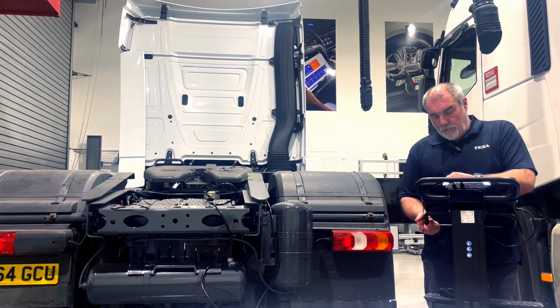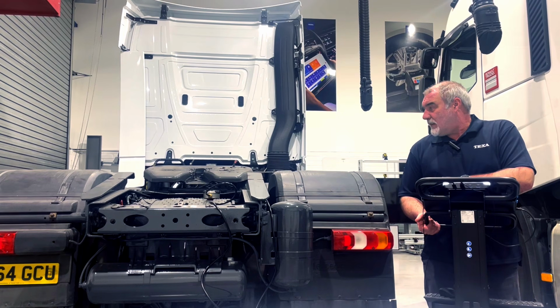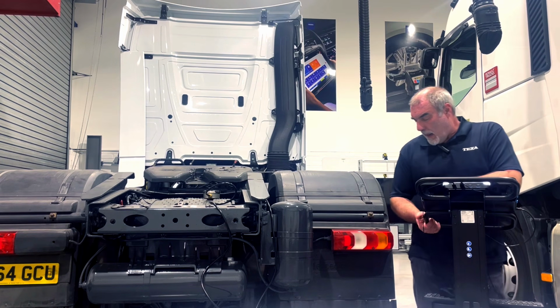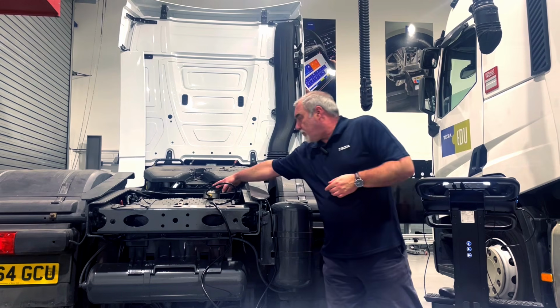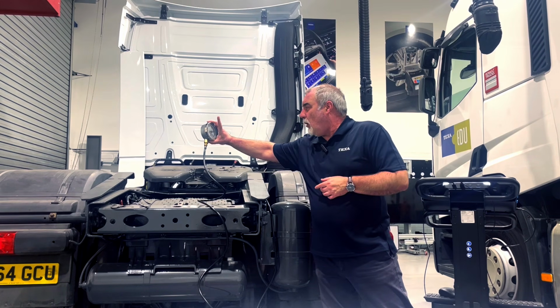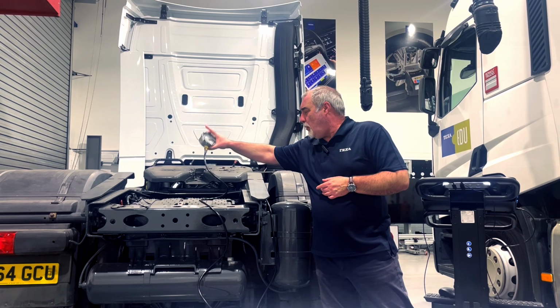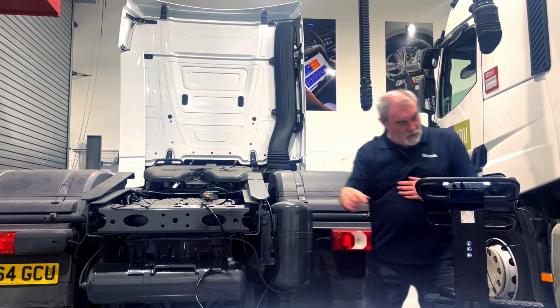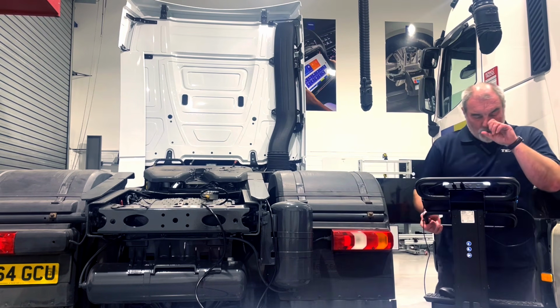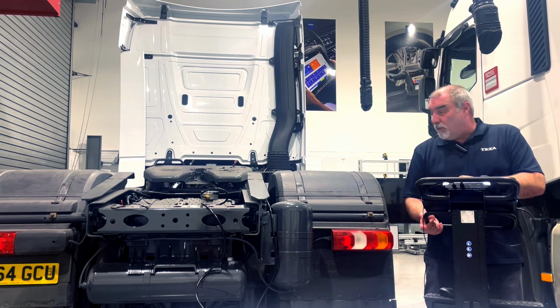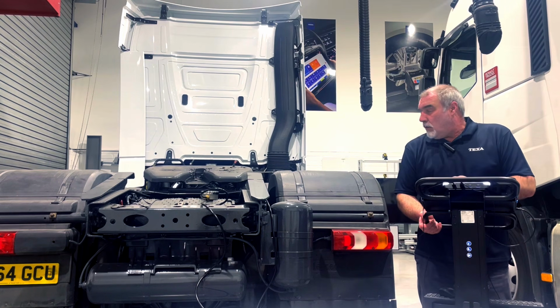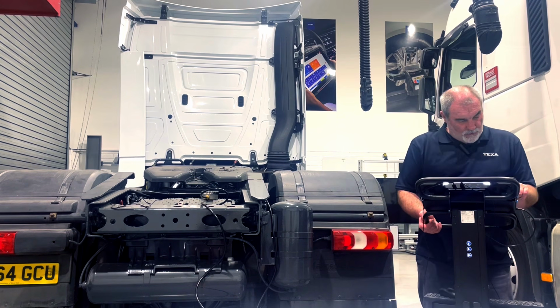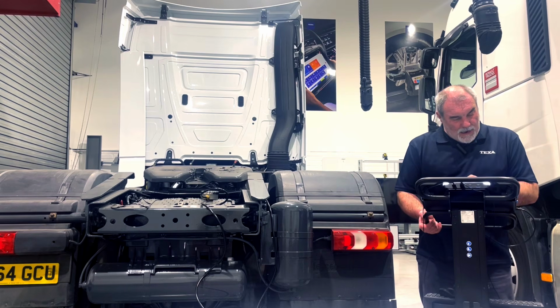Still going up. And that's it, we're no longer going up. I now check on my gauge and I'm not above 3.5 bar, I'm just below 2 bar on my pressure gauge. So I'm quite happy with that. It says at no point should it go above 3.5, so we're perfectly okay. We hit the select button.